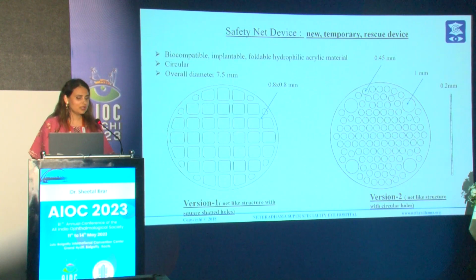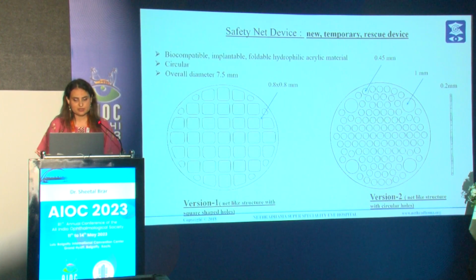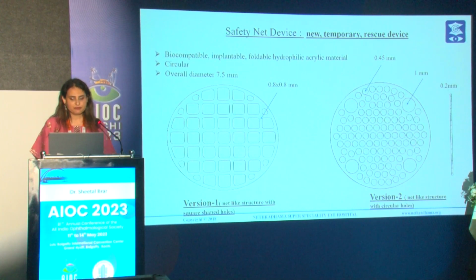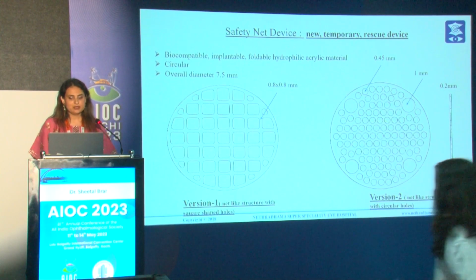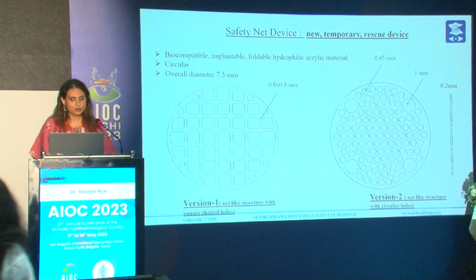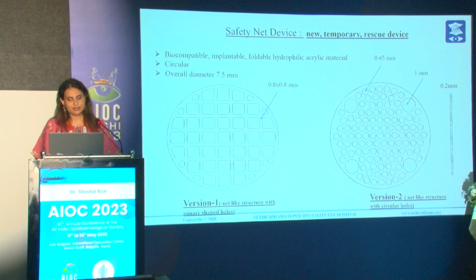So on the left side, you see version 1 of the device, which is a net-like structure with square-shaped holes. The holes were square-shaped with a size of 0.8 by 0.8 millimeters. On the right side is version 2, which we are currently using. This is a little different. You can see that there are 4 bigger holes in the periphery, orthogonal, 90 degrees to each other, and each of these holes is 1 millimeter in size, and the rest of the device is filled with smaller holes of 0.45 millimeters, and the overall thickness of the device is 0.2 millimeters.